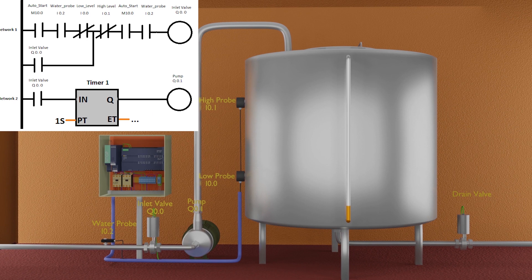This means that if we turn on auto start bit M10.0 from HMI and water probe I0.2 is sensing water in the inlet pipe and water level is below than the low level probe I0.0, it will turn on the inlet valve Q0.0 and water comes towards the pump.